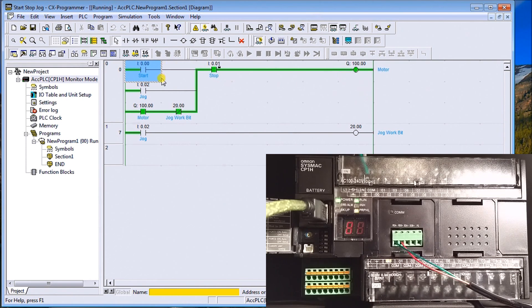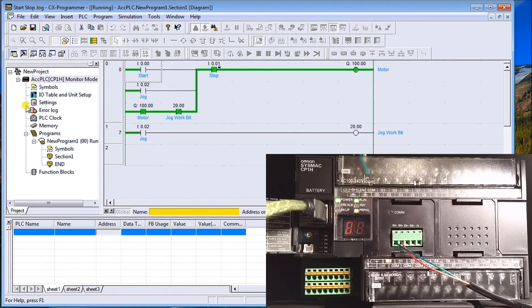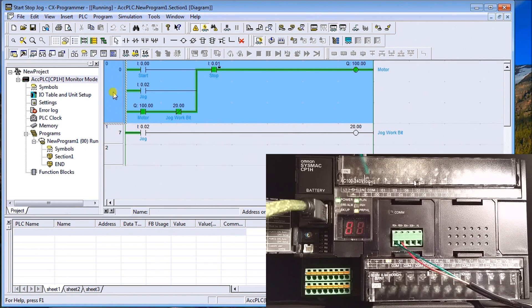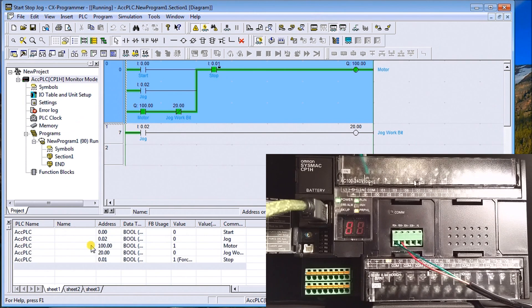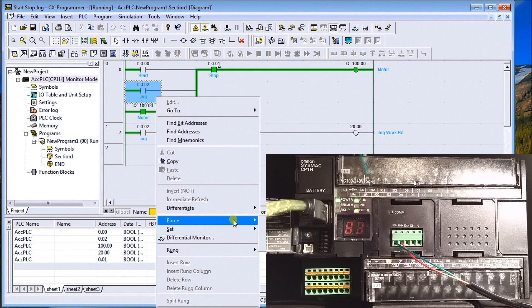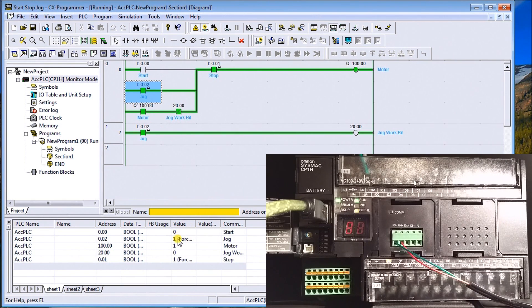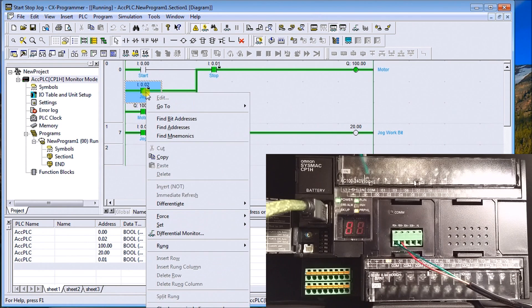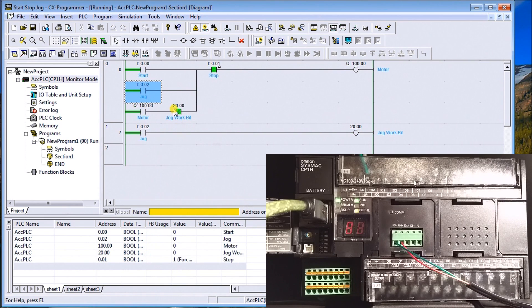There's a Watch or Toggle Watch window up here in the icons. This is the area where we can monitor bits in the PLC. I take a rung, left-click and drag it over to the Watch window, and it brings up all the Boolean expressions so I can see the exact value of each one. When I hit jog and force it on, the value shows as 1 — Forced. Then I right-click, force cancel, and it turns off. It's an easy way to monitor all the different bits.